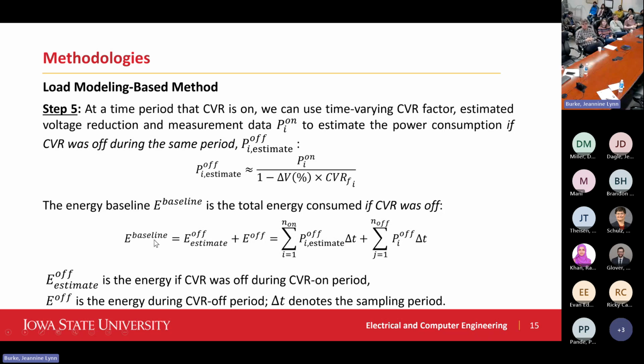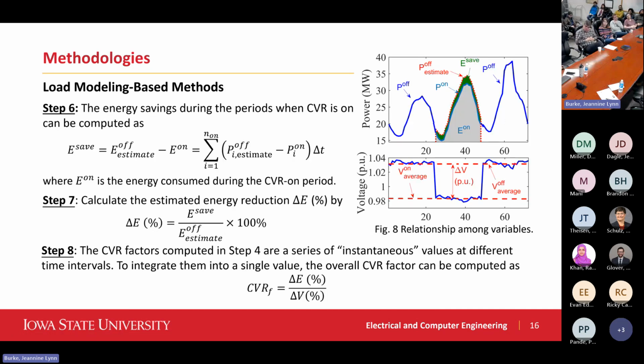Then you can get the energy baseline, basically just using this plus some CVR-off data. Then you reconstruct this energy consumption line. You reconstruct this red dotted line, and then you can calculate the difference between the dotted line and the blue line, and you get the green area. Then you can calculate energy saving, just E-save divided by E-off estimate.